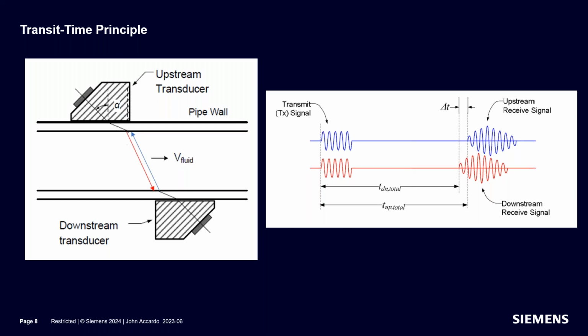But when there's flow moving in the pipe, the signal going downstream is accelerated by the flow, and the signal going upstream is delayed by the flow. As a result, there's a difference in time between the two signals. That difference in time, which is known as delta T, is related to the speed, or the velocity, of the flow moving in the pipe. So technically, the flow meter is a speedometer. It's just measuring flow velocity and then ultimately converting that velocity into a volumetric rate of your choosing.